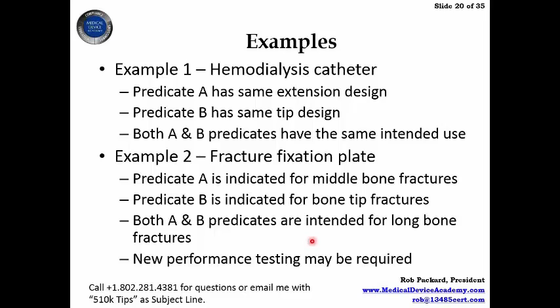I even actually happened to audit the company that made it. Both A and B predicates are listed for this new novel bone fixation plate that can be used for either type, but you're going to have to provide some new performance testing data. You might have to do some cadaver labs and show that it can be inserted without a problem for those patients in both locations, different size ranges. So you can have small patients and large patients. It's going to work well for all with different size considerations. That's some of the information you're going to provide for that performance testing data to show it doesn't add new risks.